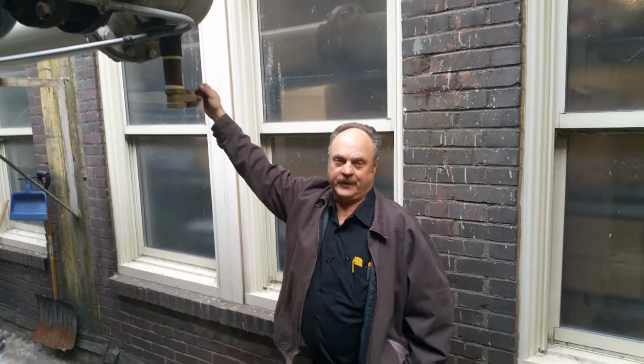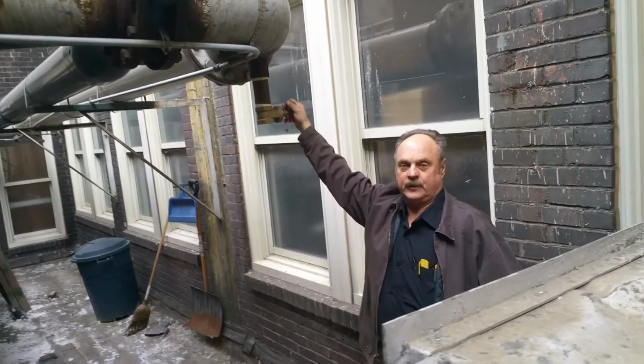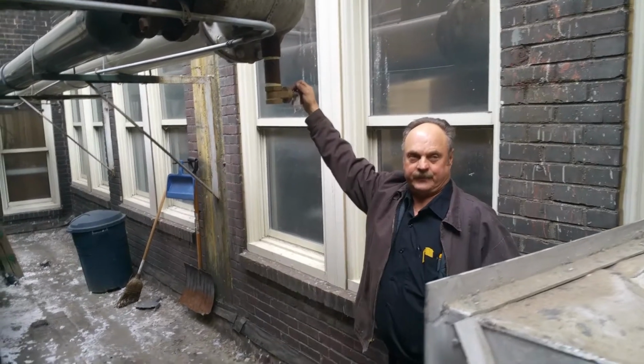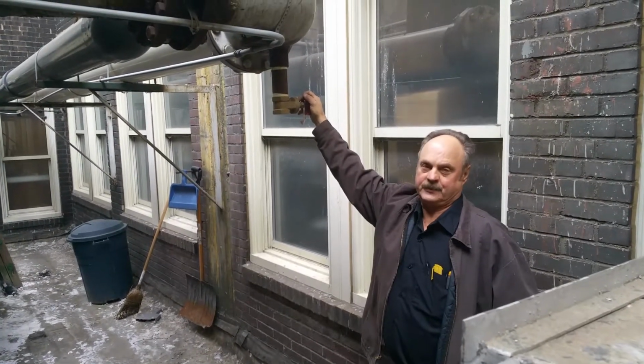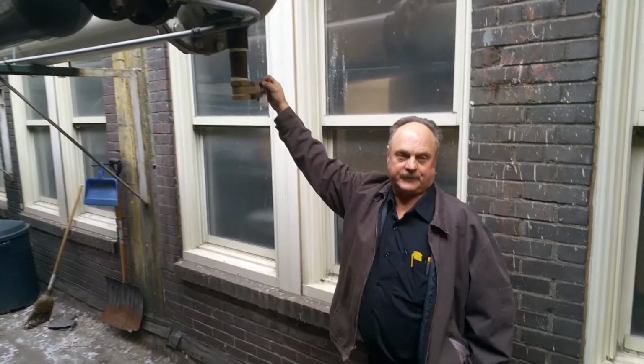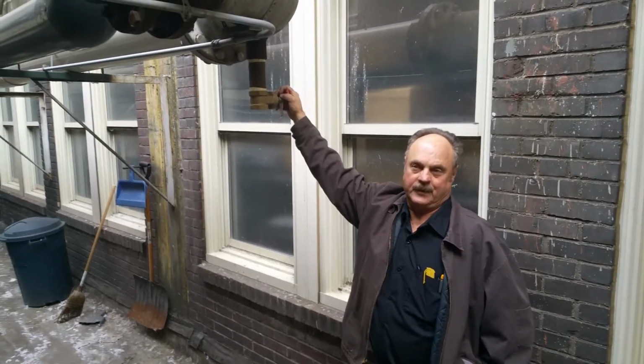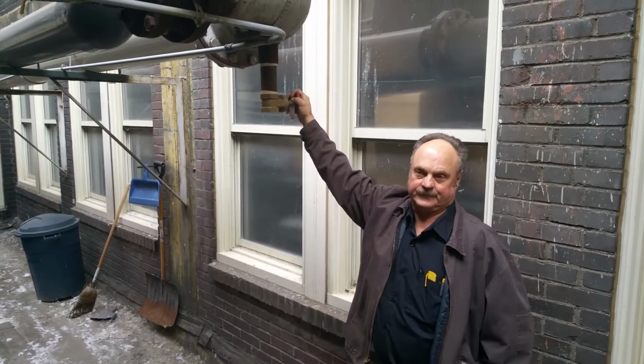Once again, we got to drain this valve. This goes to the cooling tower condenser, which goes down through the chillers. We drain this because we don't want the pipes to freeze and break during winter months, so we drain all the water out of the system.